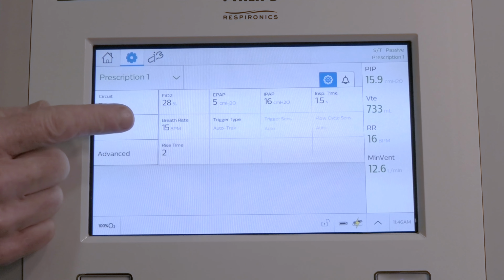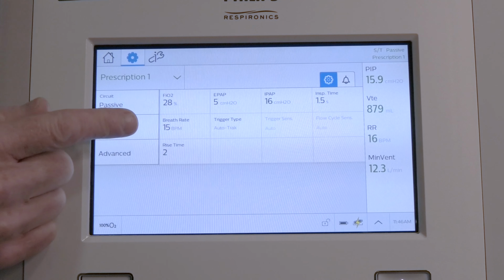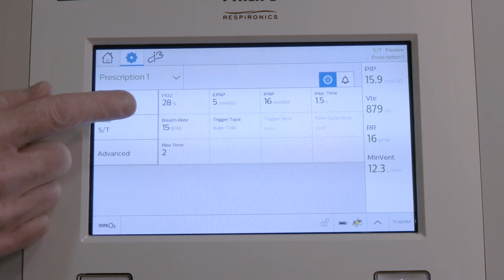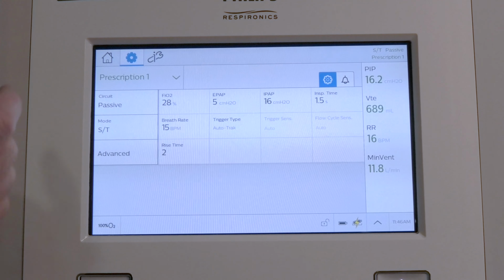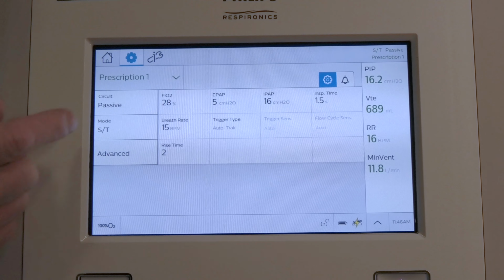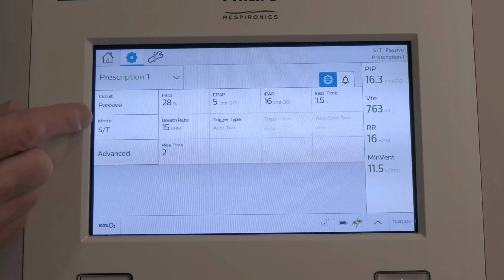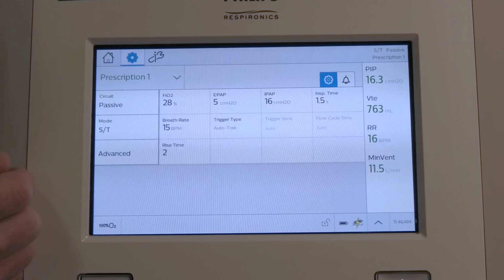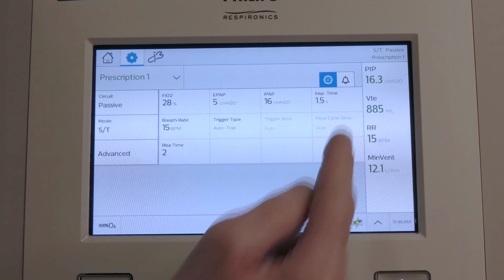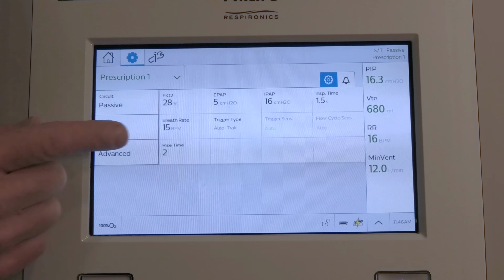Your breath rate is your backup rate, and that will kick in if your patient takes less than 15 breaths in this instance. BTS tell us 15 breaths a minute is a good backup rate to have. We can ventilate people well enough to keep their CO2 down with a backup rate of 15. So we usually set that at 15, and then we have to set our inspiratory time for our backup breaths.